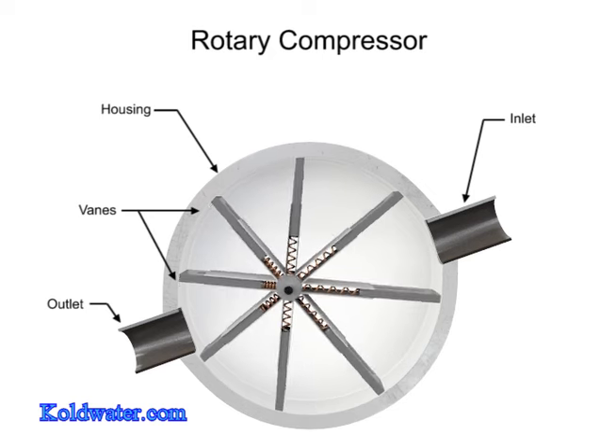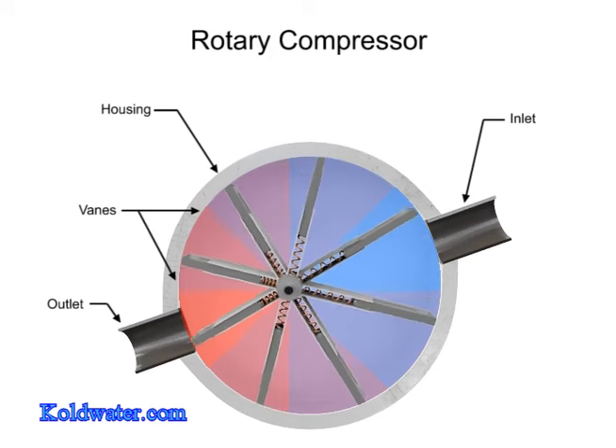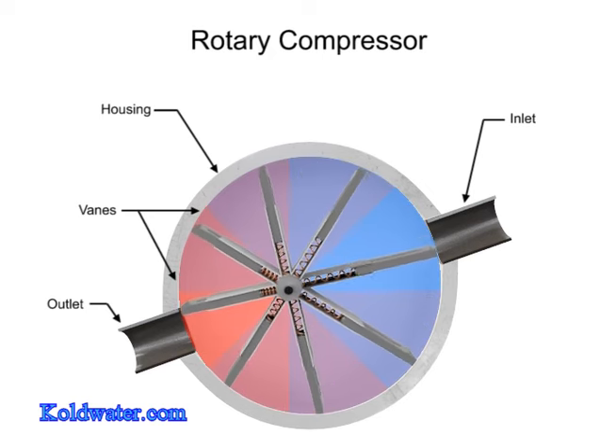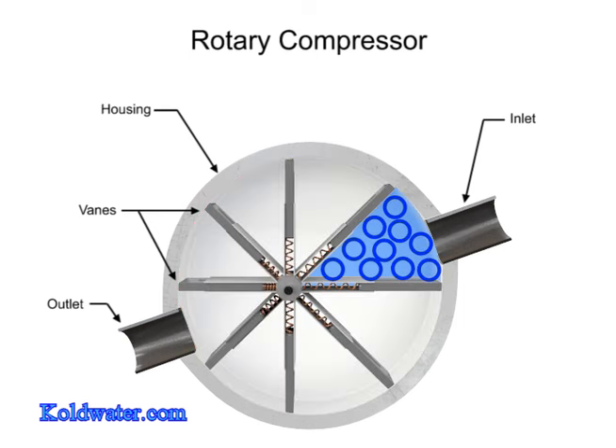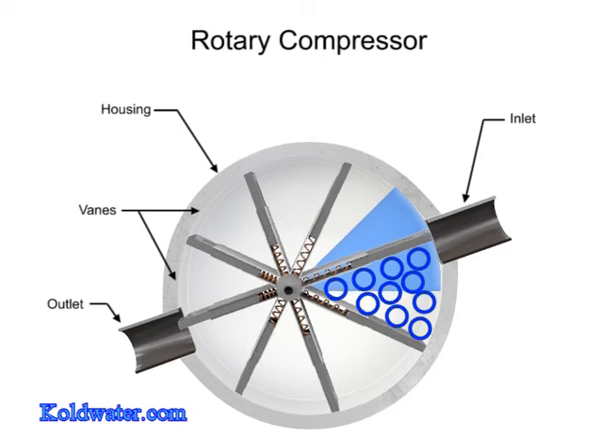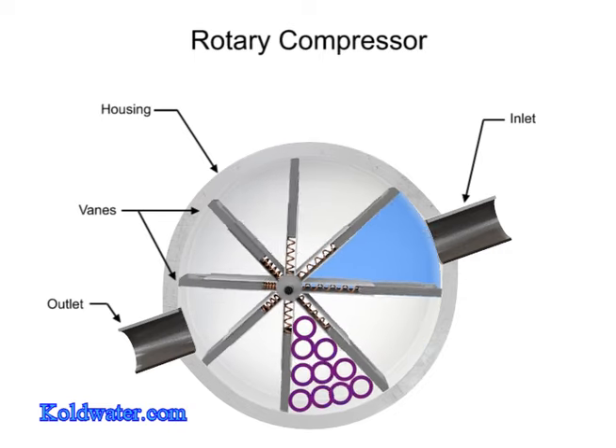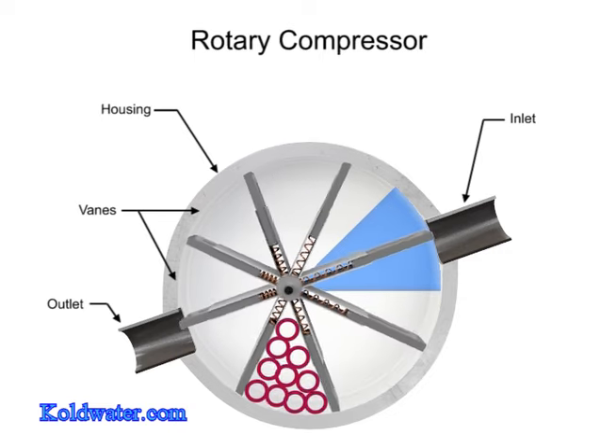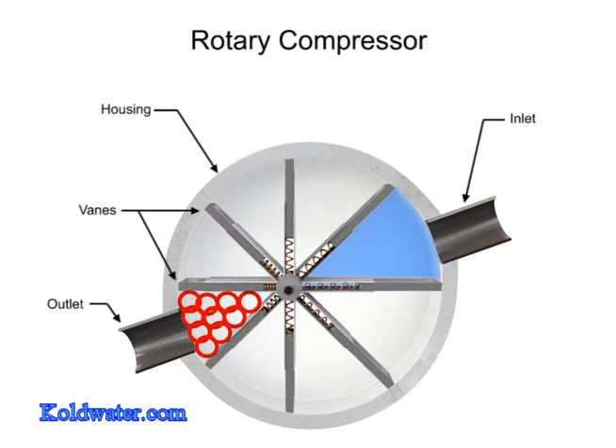As they do, they create chambers within the cylinder of varying sizes. Air enters at the largest chamber; as the vanes rotate, they retract, causing the chamber to get smaller and compress the air. Air exits at the smallest chamber.